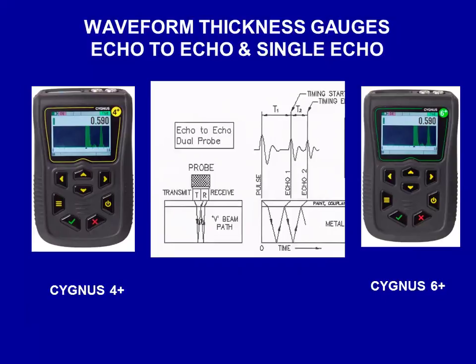And that's why, when you use the gauge, there's a bar system. When you turn the gauge on, there's a flashing bar on the left part of the screen, which means the gauge is on and it's cooking. To the right of the decimal point is a two-bar system. You see the first bar light up, it means you've got the sound in the metal. You see the second bar light up, and you've got the second echo. And when you see the third bar start flashing real fast, it means you're close to getting the measurement. Just rock it, tweak it, move it, romance it.